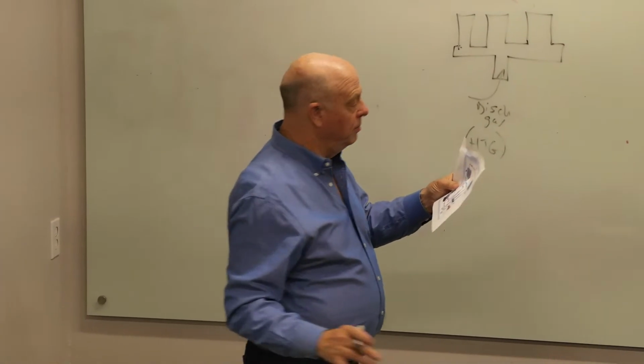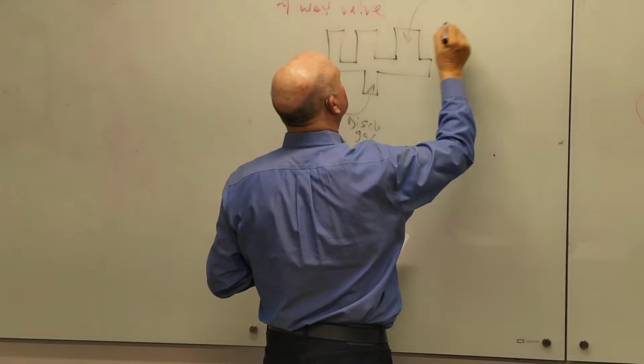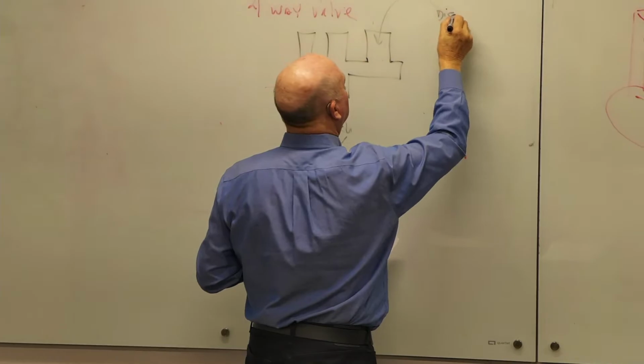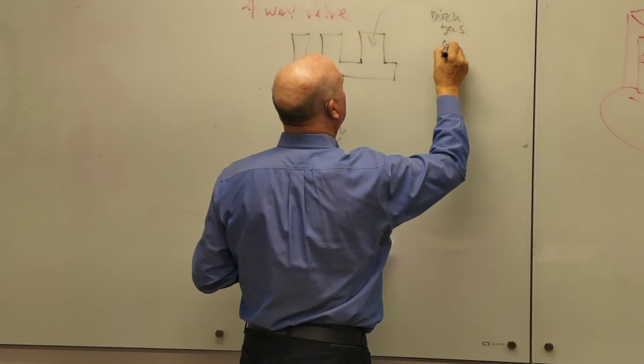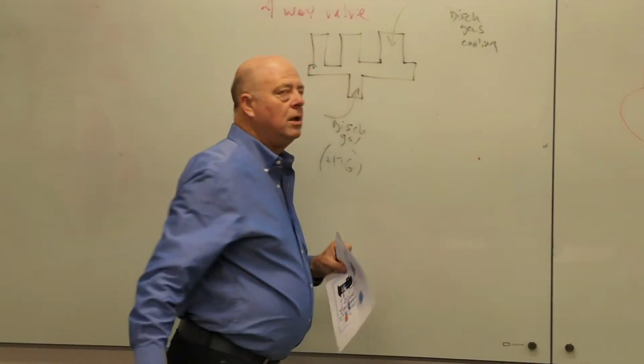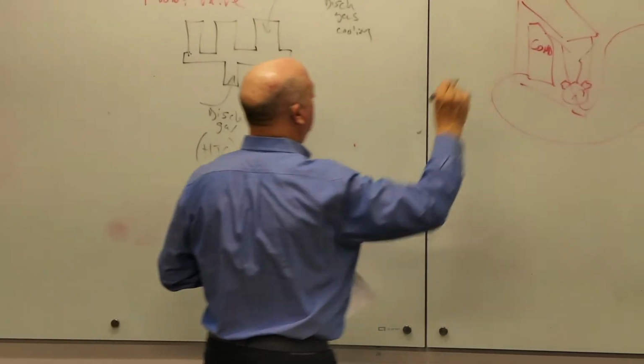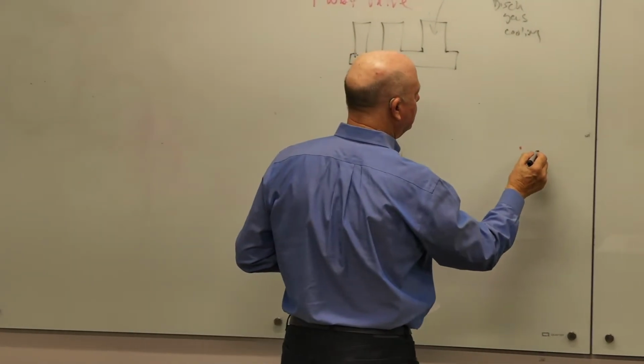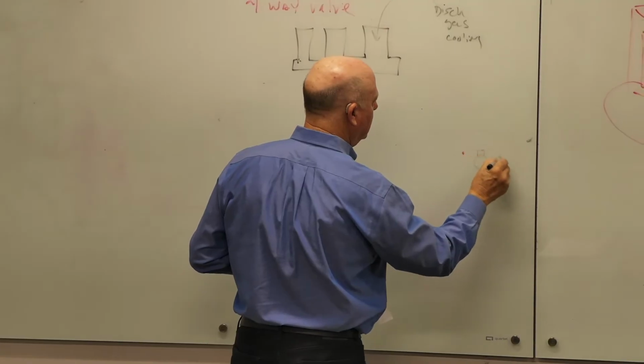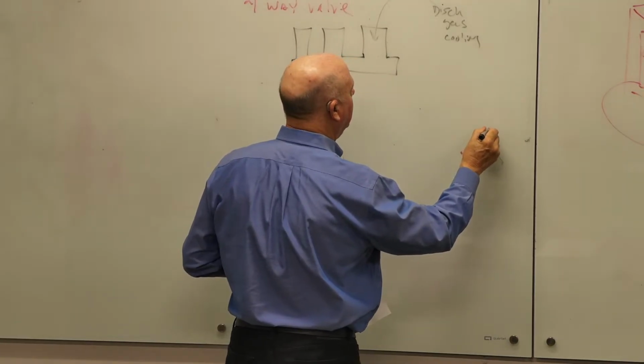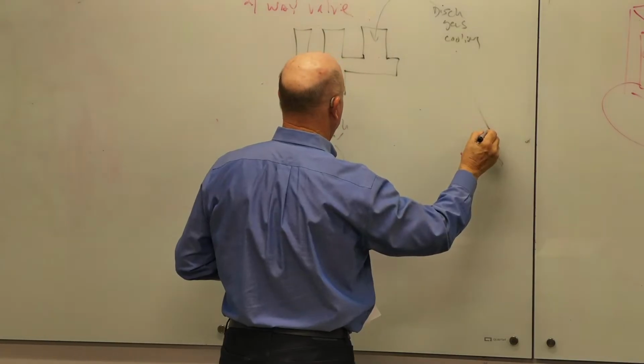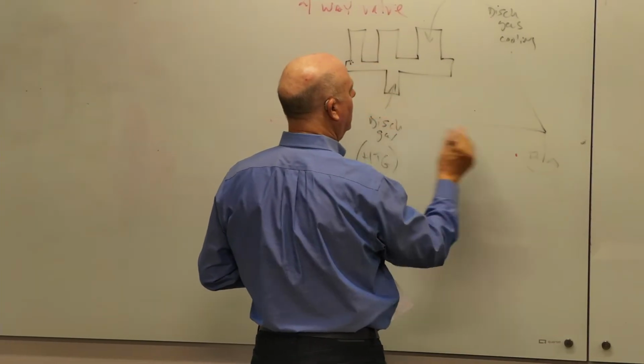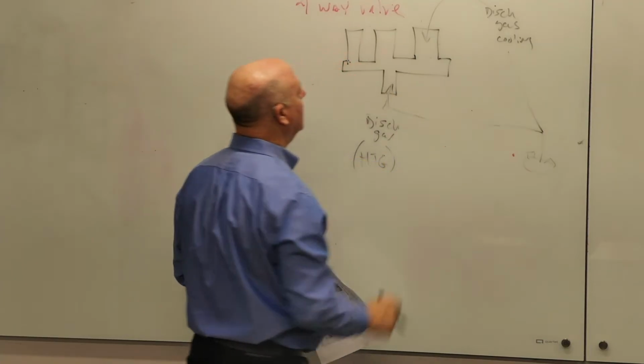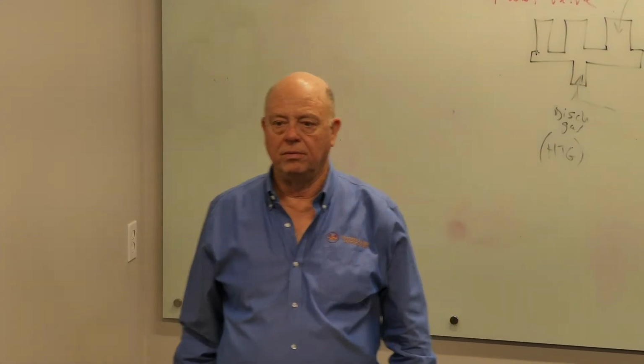In the cooling mode, that means off the compressor in the unit, we've got to actually split the line. So here's our compressor, here's our discharge gas, and it branches. So the gas can either end up going in one valve or the other. How does it know?